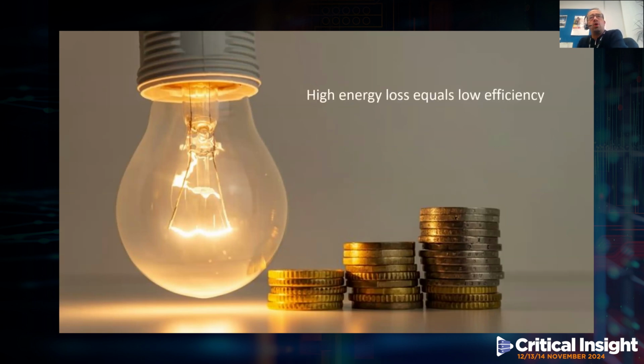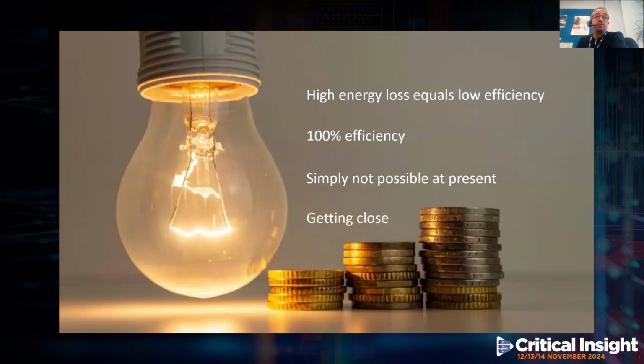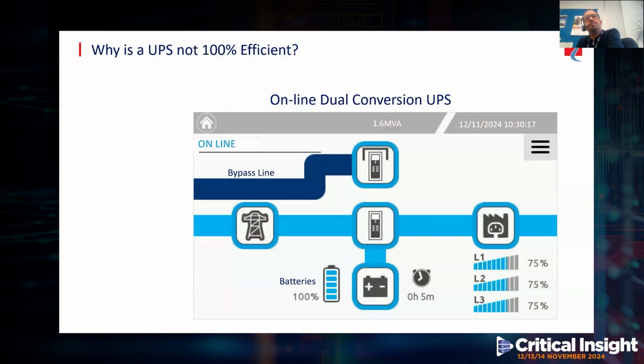Basically, the greater the energy loss, the lower the efficiency, the higher the costs. Every UPS manufacturer ultimately strives to achieve 100% efficiency. However, sadly, due to the current technology and, of course, the laws of physics, this is simply not possible at present, albeit through advanced UPS design and the very latest in component technology, we as a manufacturer are getting close, along with many others. Now, the question we need to ask is, why is a modern UPS not already 100% efficient? Well, due to the way in which the online dual conversion UPS system operates, losses are inevitable. Basically, the UPS functions by making two power conversions, hence the name dual conversion.